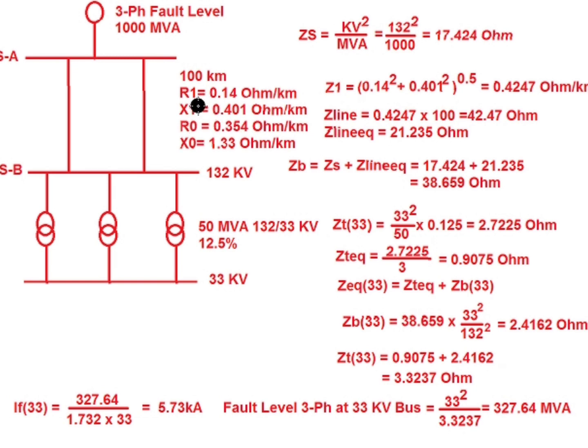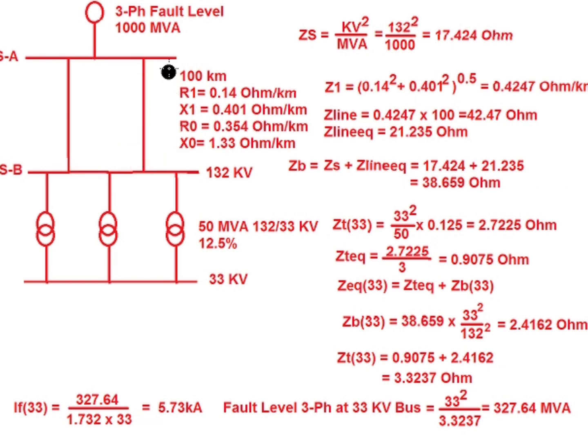Since R1 and X1 are known, we can calculate the positive sequence impedance: Z1 = √(R1² + X1²) = 0.4247 ohm per kilometer. Since the line length is 100 km, the line impedance is Zline = Z1 × 100 = 42.47 ohm. Since there is a double circuit line — two lines connected in parallel between substation A and substation B — the equivalent line impedance is 42.47 / 2 = 21.235 ohm.